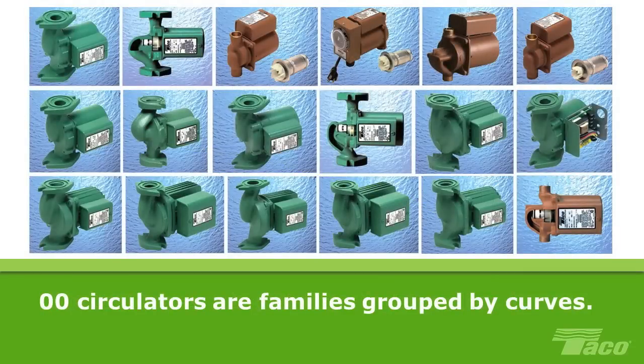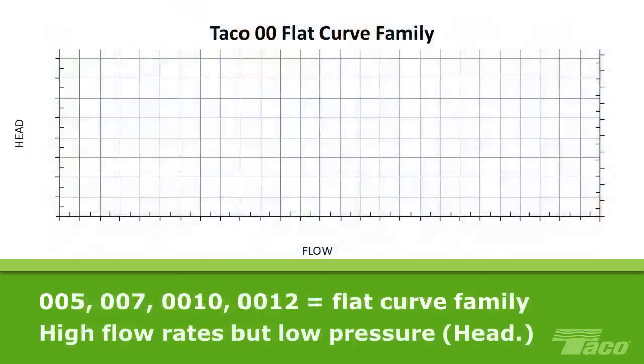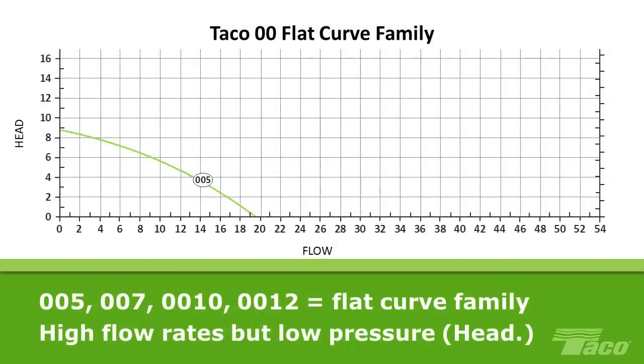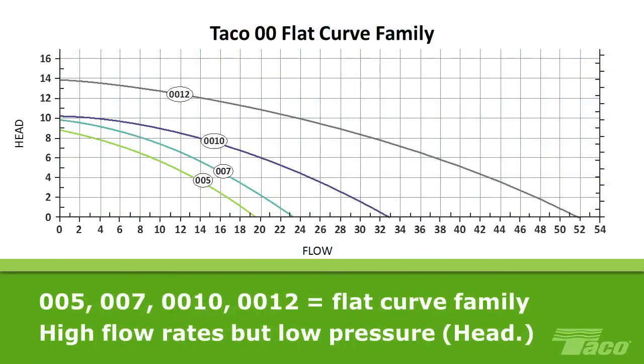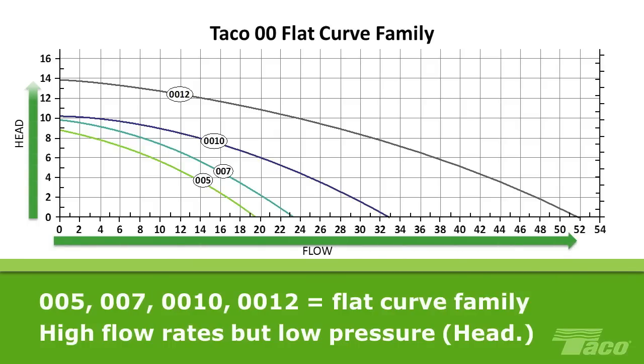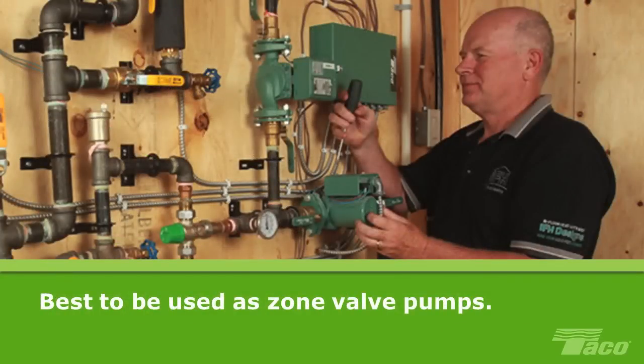It's helpful to think of Taco 00 fixed-speed circulators in terms of families grouped together by their curves. The 005, 007, 0010, and 0012 circulators are all members of the flat curve family — they can produce high flow rates but relatively low pressure. A smaller flat curve pump, such as the 005 or 007, is ideal as a system circulator for zone valves in standard residential jobs or as a zone pump. The larger flat curve pumps, like the 0010 and 0012, are designed for larger residential jobs or light commercial applications.